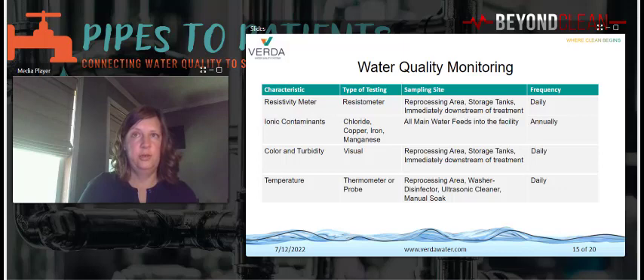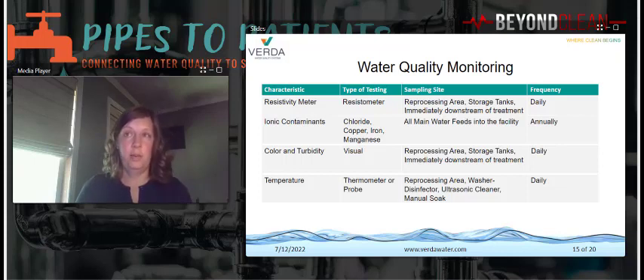Many facilities use independent testing laboratories to test water samples collected in the SPD. The results received from these outside labs need to be carefully interpreted. Testing on ultra-pure water, like critical water, has very specific requirements, and many typical lab tests are not optimized for these samples. Invalid results or inaccurate measurements can easily happen.